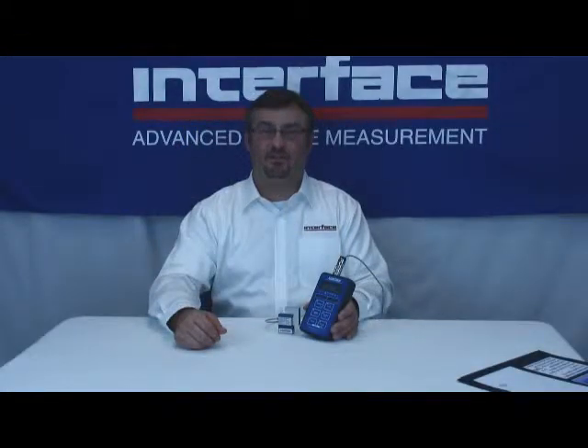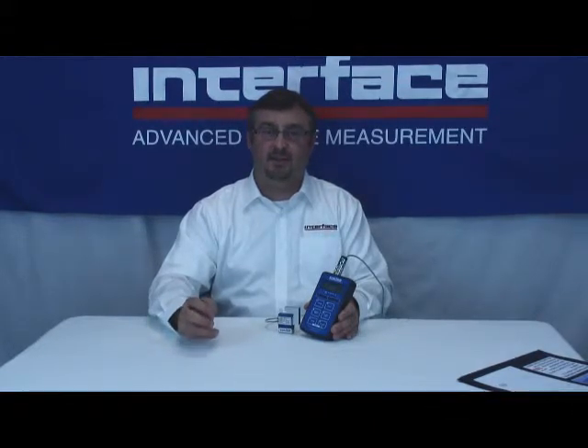I mentioned TEDS earlier, but I'd like to briefly expand on that topic. TEDS stands for Transducer Electronic Data Sheet, and it's a feature where a digital instrument can read a chip installed in the load cell, read the calibration characteristics of the load cell, and then self-calibrate. So basically, when you plug in a load cell that has a TEDS chip installed, and the TEDS feature is turned on in the meter, when the meter sees the TEDS chip, it finds it and self-calibrates, and then you're ready to go.